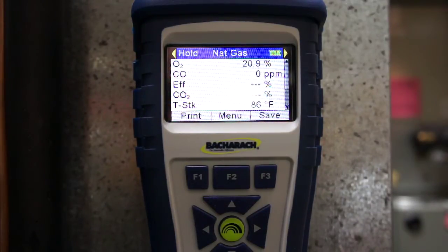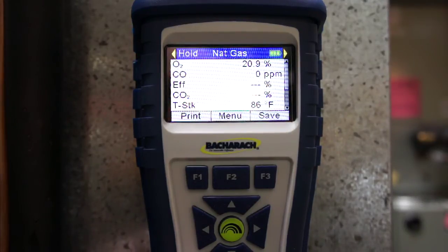Okay, so we have the 90 plus furnace here going through a post purge, and I'm going to go ahead and push the run key so we can look at the response of the instrument. And the pump started on the instrument. You can see our O2 is starting to bounce around a little bit right there. Stack temperature starting to increase, which is all a good indicator that we're actually starting to make a measurement. There goes the burner, it just lit off.